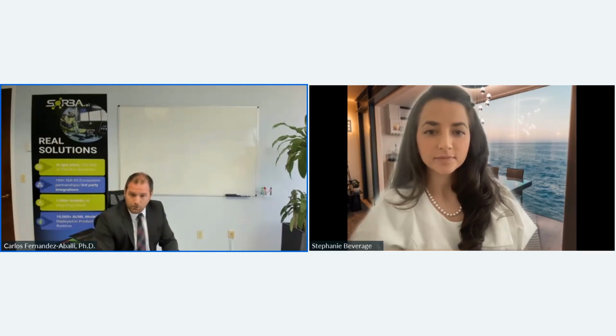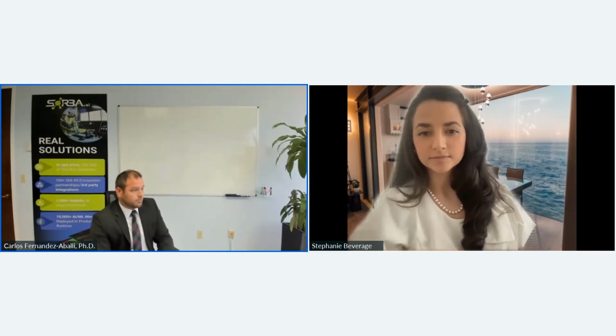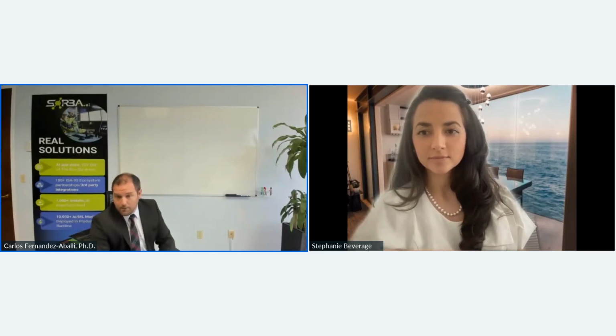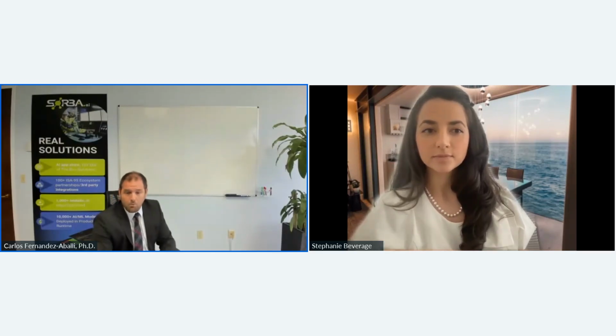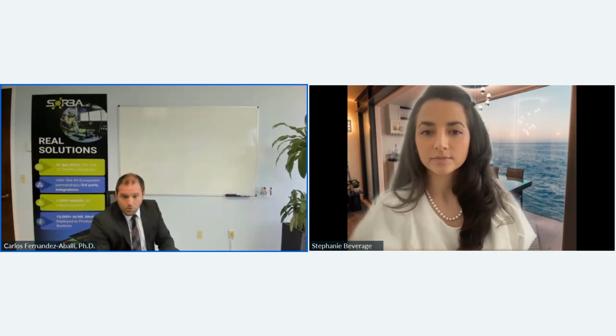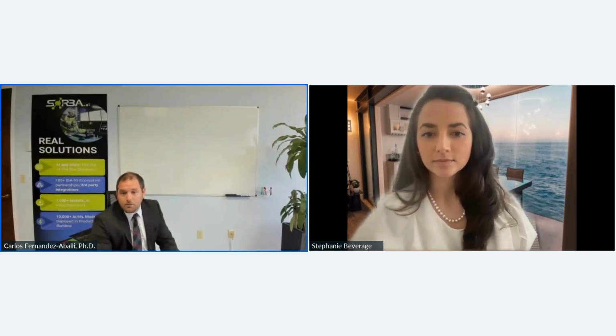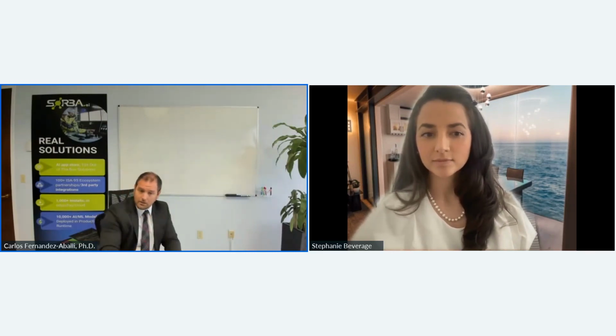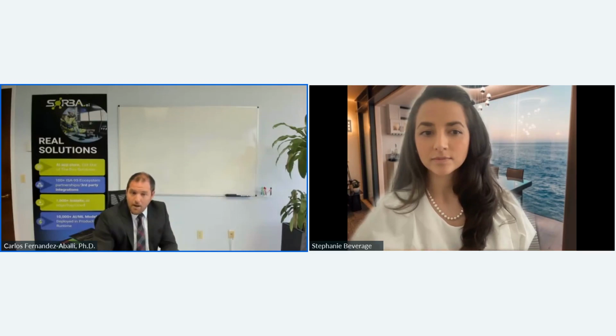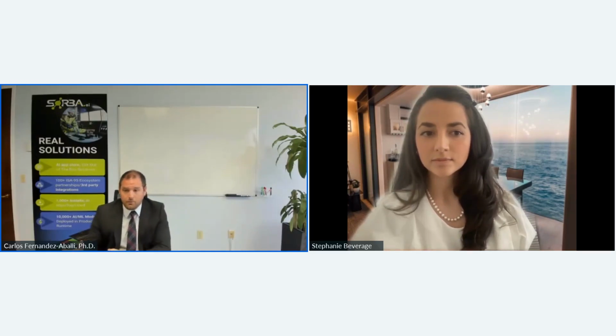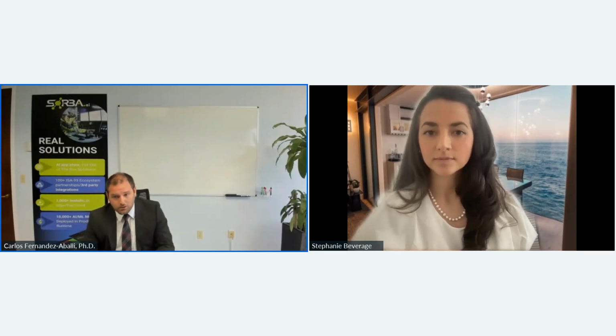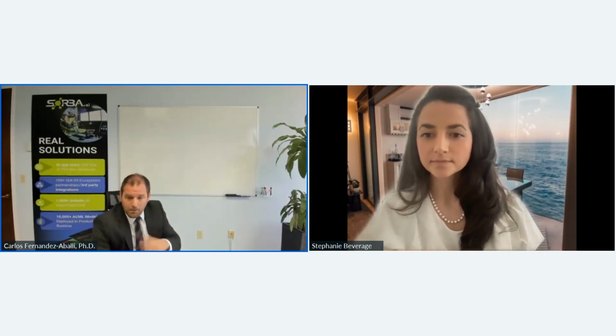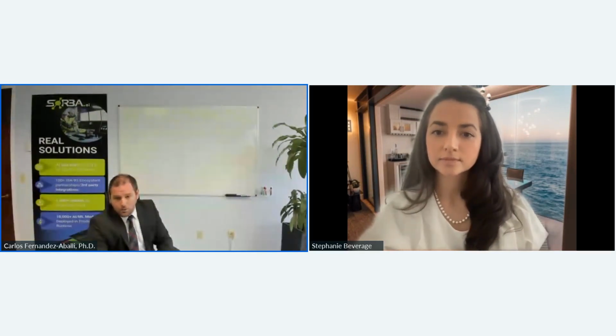That said, it would be the same general process. For example, in the case of a CO2 cycle, which is quite common now and becoming more popular, these scripts would work almost to the same point, especially if you can measure at the COP level. We would have to revise the cyclic behaviors, the power behaviors, but if we had the measurements of the loads and the electrical power provided to the system, we could go ahead and very quickly implement the solution with these same scripts and templates.